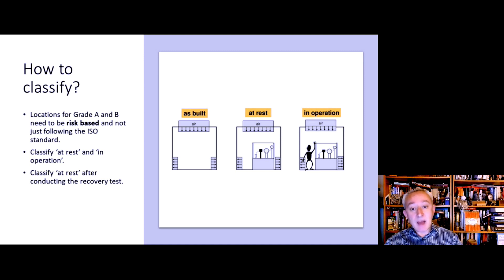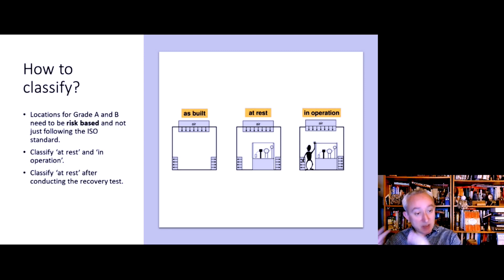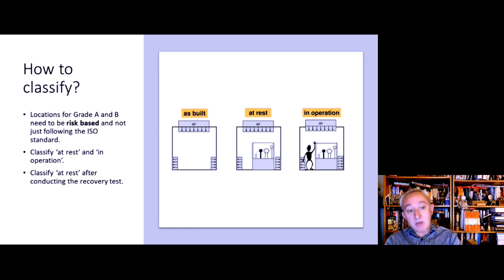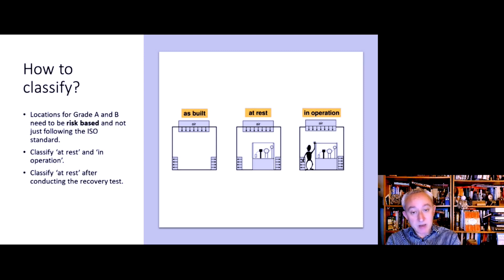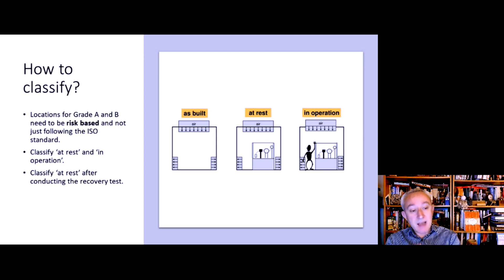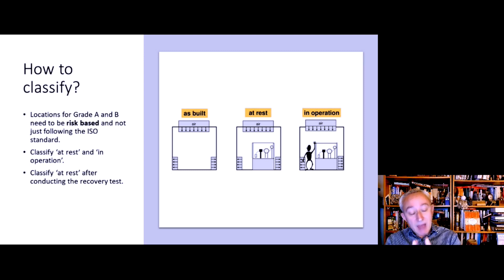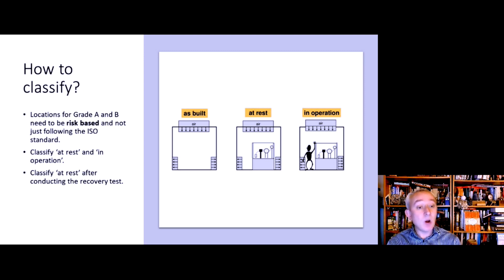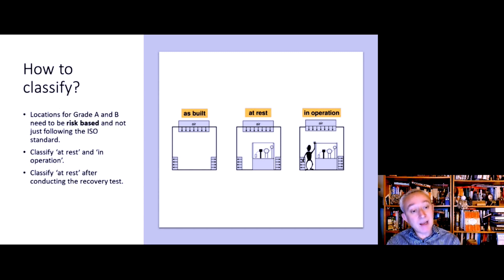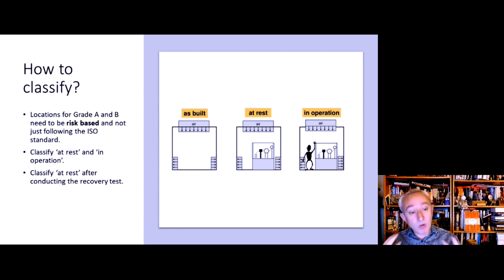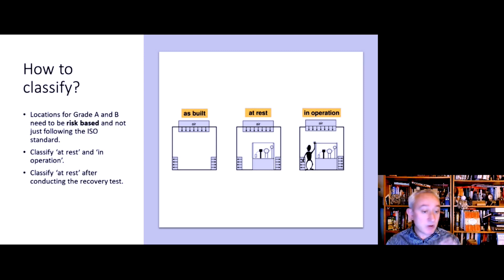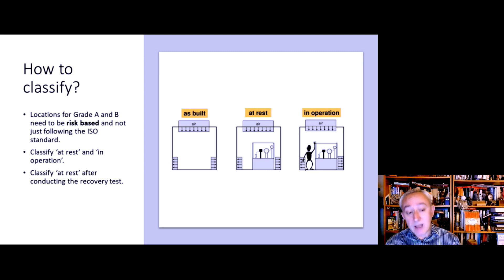In terms of how to classify, there is an as-built step which is for a newly built clean room, but assuming that we're dealing with an existing facility, then there are two operational states that we need to assess: at-rest and in-operation. For that exercise we need to use a number of particle count locations, and the ISO 14644 standard will guide us for that. But the Annex says for grade A and grade B, we often need to go beyond what the ISO standard is requiring and add additional locations for critical areas like point-of-fill and stopper bowls for a conventional filling area or inside an isolator. We need to justify those through a formal documented risk assessment.